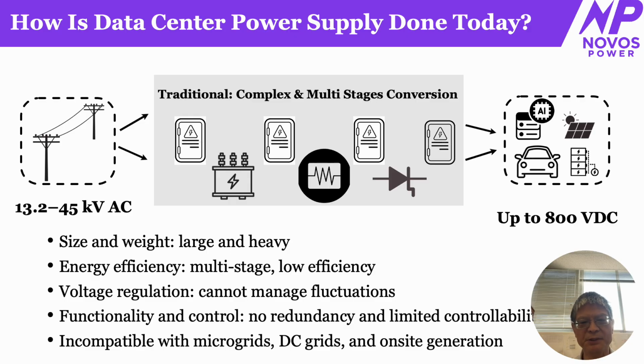And this process has been working, however we do have a few issues. One is the large size and weight of the system. Second is energy efficiency, because of the multi-stage power conversion of the system. Third, the traditional transformer is a passive device - it does not have the function of voltage regulation or frequency control, and it cannot manage the power fluctuations of data centers. So the functionality and control is very limited. There's no redundancy, there's limited controllability, and it is incompatible with our modern microgrids, in particular DC grids and on-site generation.